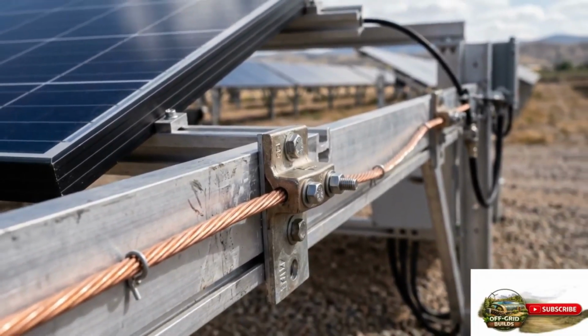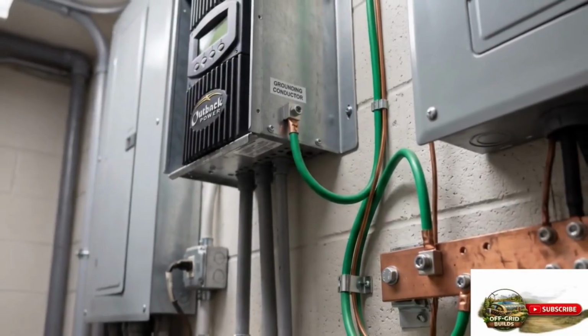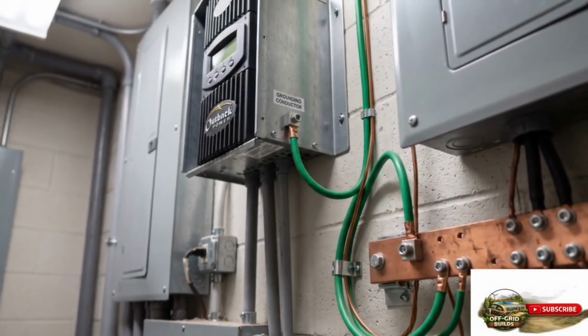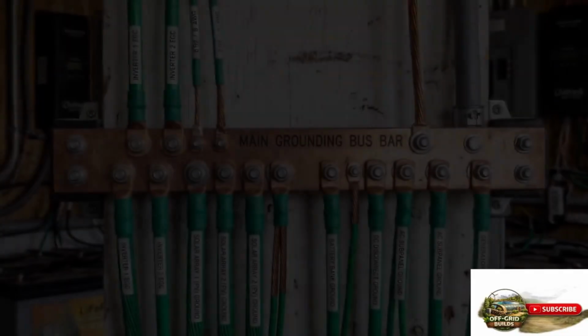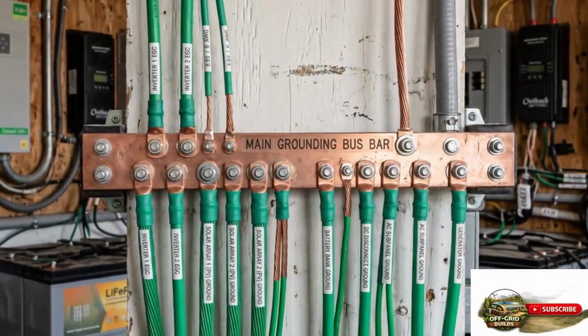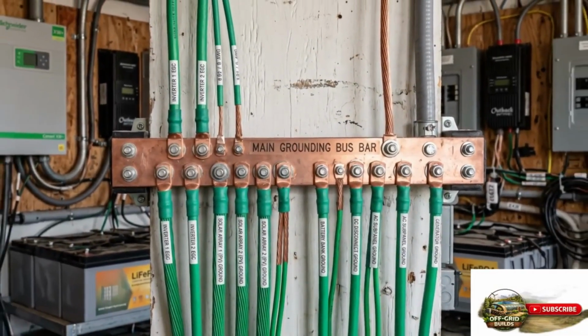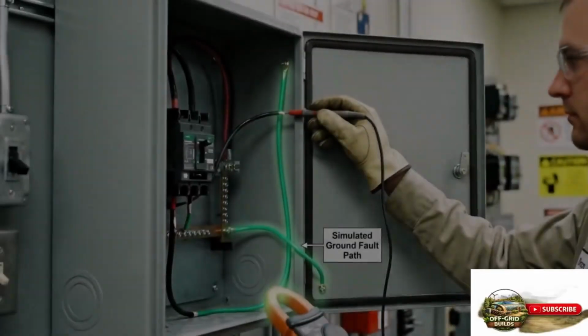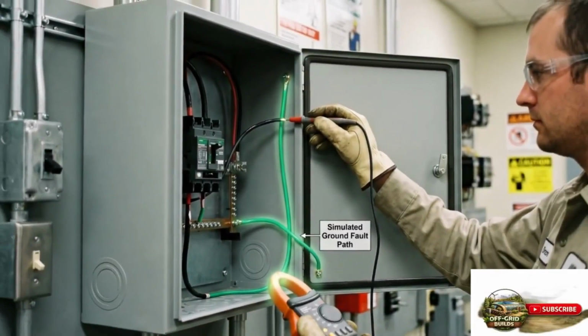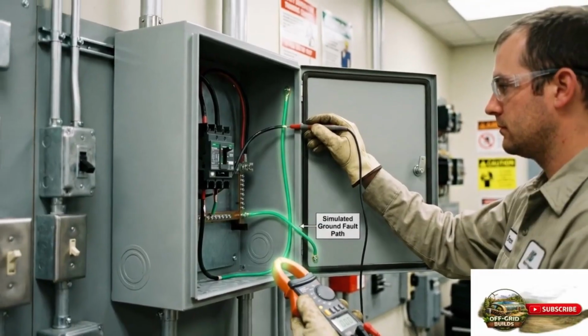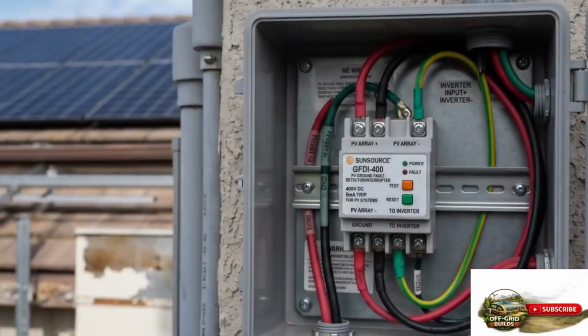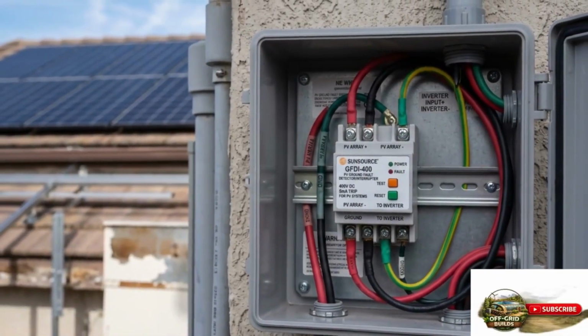In a photovoltaic system, equipment grounding connects all metal enclosures, conduit, mounting structures, and equipment frames to a common grounding electrode system that is connected to the earth. This means that if a hot conductor contacts any metal surface in the system through a fault or accident, the current flows to ground rather than through the body of a person who might contact that surface.